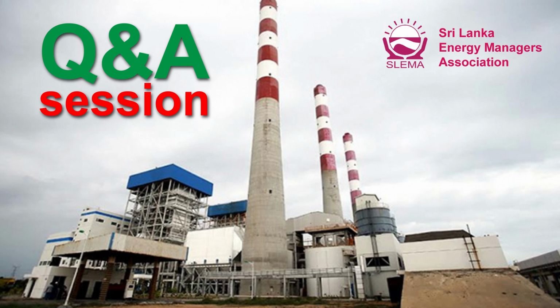make our power system self-sufficient. So pump storage is going to support the peak demand dispatch, because now if there is a peak demand, of course the pump storage power plant can run, and the other way around, when the renewable energy power plants are available, due to their intermittent nature, you can run the pumping mode so that you can use it to store water, so that at a later stage, particularly at peak demand time, you can use it to generate electricity.